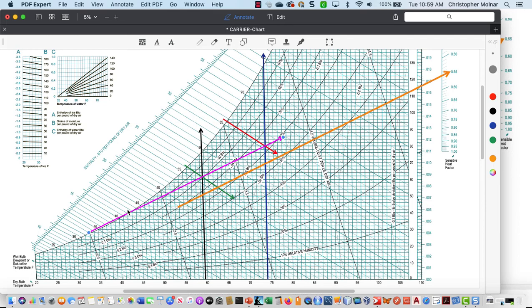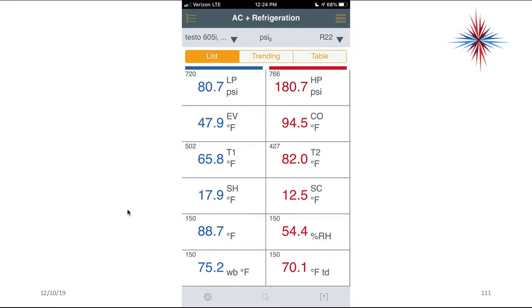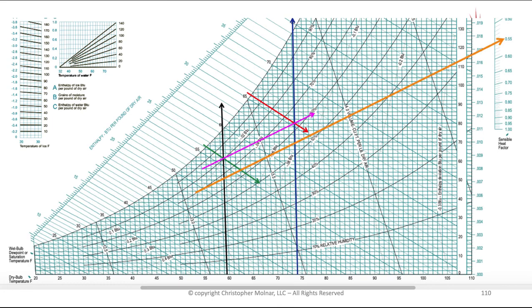Since the evaporator saturation temperature is 10 degrees under the ADP, it should be around 33 degrees. However, the actual evaporator saturation temperature for this site is 47.9 degrees — so it is not correct. There is a cooling problem somewhere in this system. We also know that superheat is very high here, and this was not a TXV system. By using the ADP and these calculations, we can figure out what the system should be doing versus what it is doing — an important troubleshooting tool.